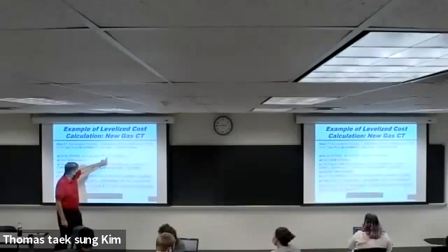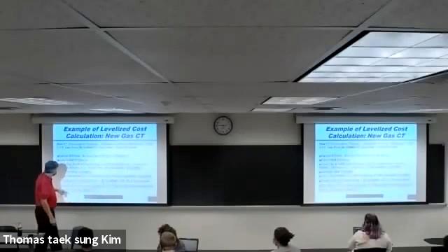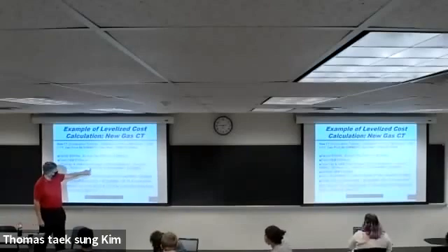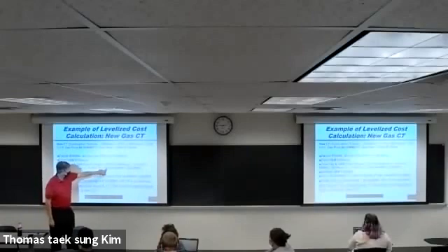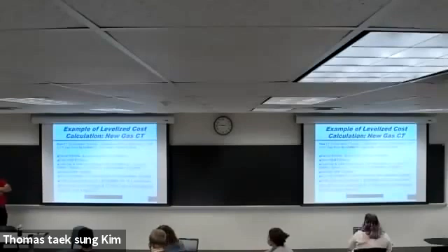So $50 a kilowatt year, and fixed O&M is $10. So the total is $60. Now we convert to dollars per megawatt hour. $60 a kilowatt year divided by 500 hours, times 1,000 kilowatts per megawatt, gives you $120 a megawatt hour. Okay. If you remember the other example, that's a lot more than a combined cycle.